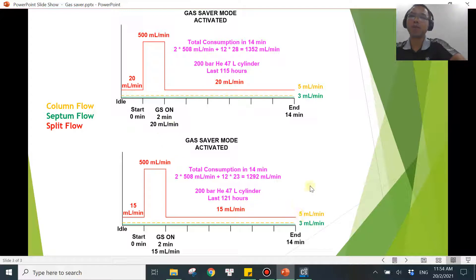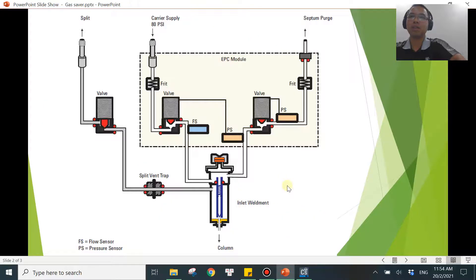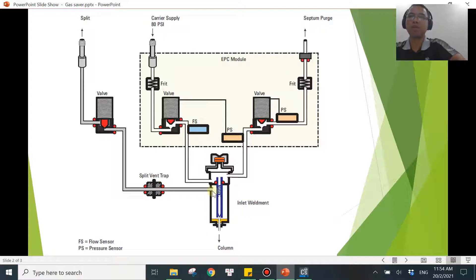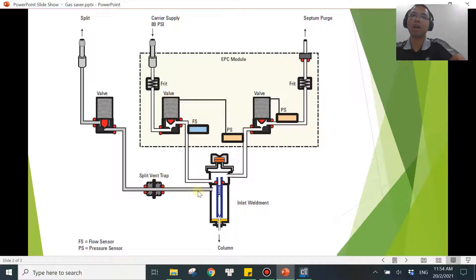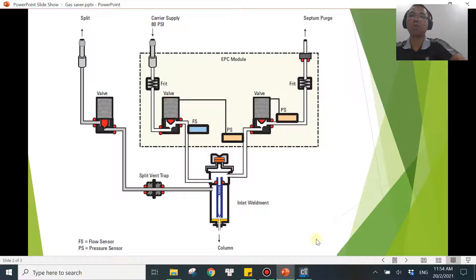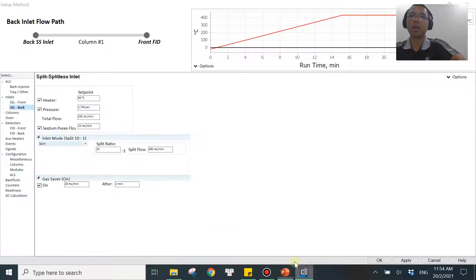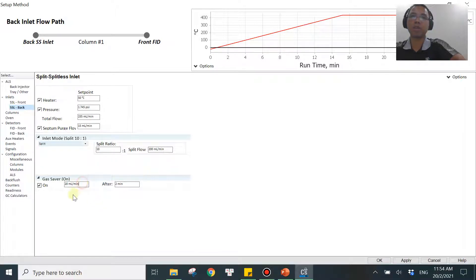You can't go lower than 15. The software will not allow you to do that. The reason is because you want to push this part over here efficiently. You don't want to have it so low. Otherwise, some of the samples may not be able to carry on the way to the split vent trap over here, and you may have some kind of blocking along the line, something like this. So that's why the software will not allow you to go lower than 15 when you hover the mouse over here. There you go, 15 mL per minute.